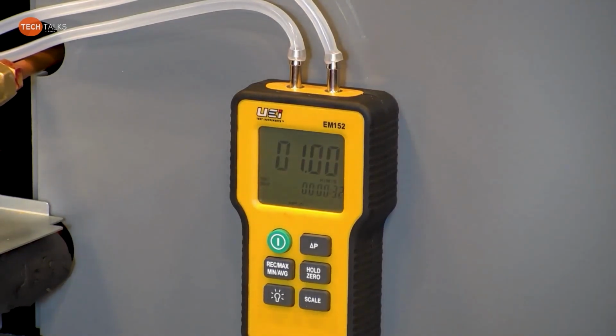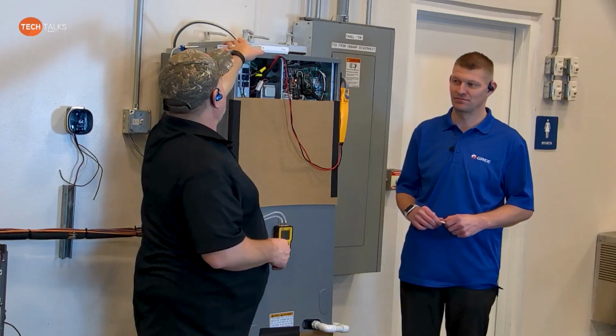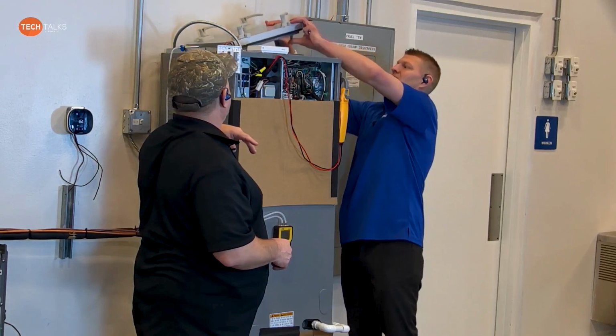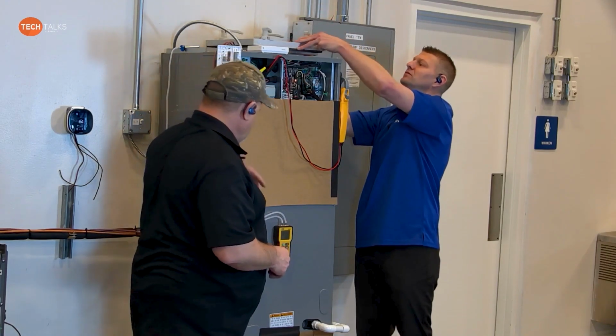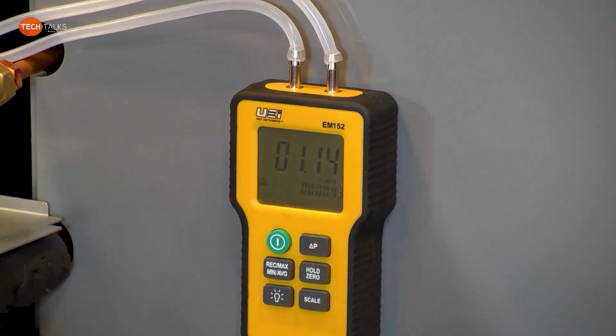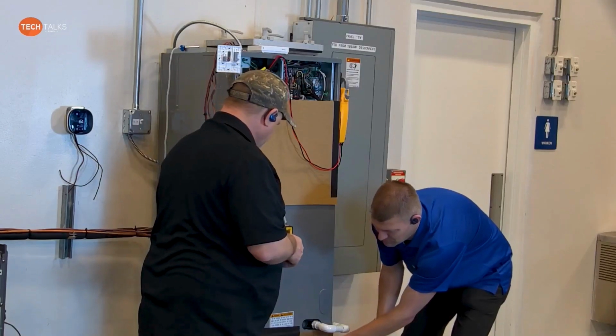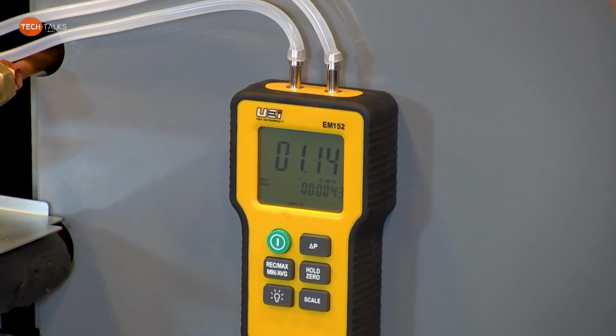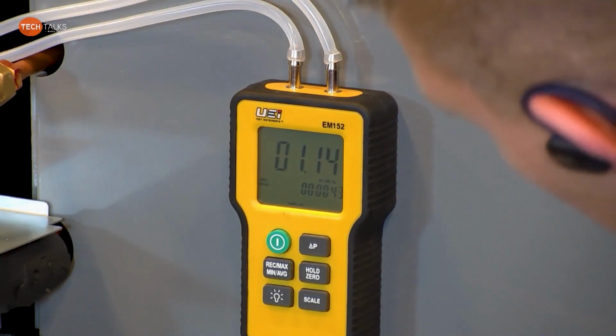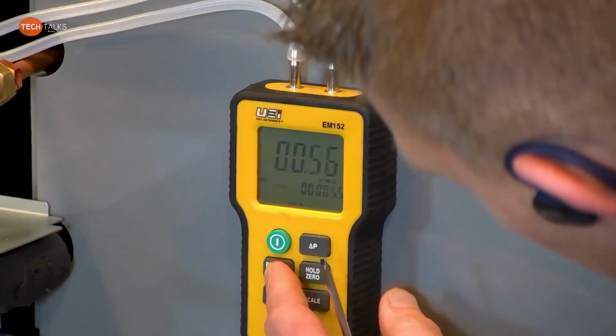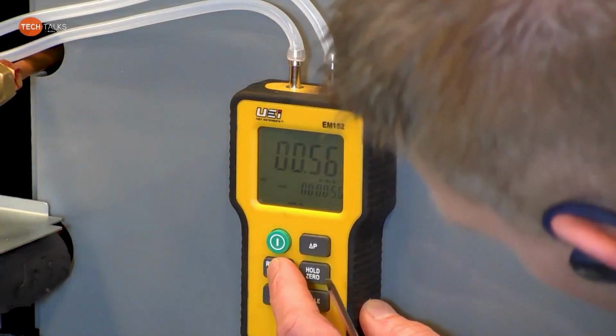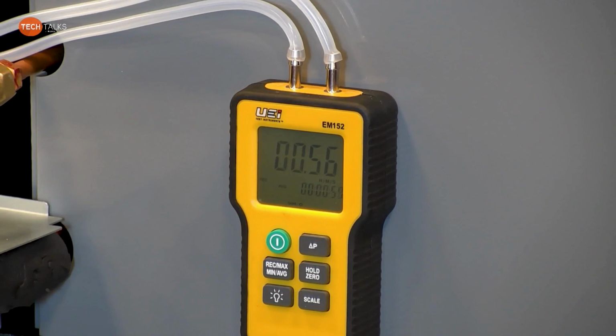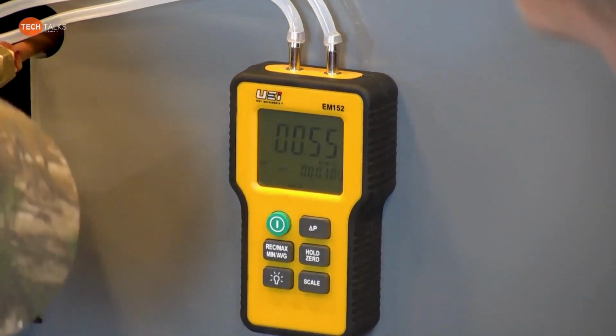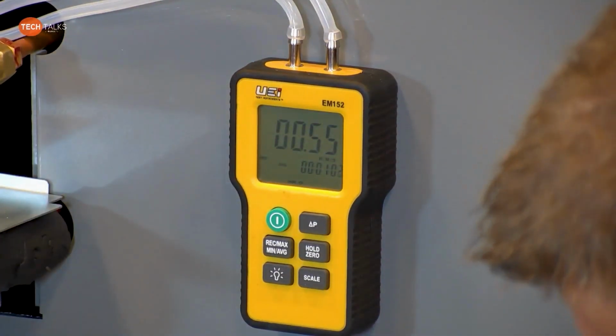Well, now we got some static. Yeah, we do. So that reiterates what I was saying. So back your damper off on the top a little bit. Don't take it off. Yeah, there you go. See if it drops any. And then back this off just a little bit. You got to give it a minute. You're still in inches of water column? Need an average. There we go. I think that's it. 0.55 now. We'll slide it back.